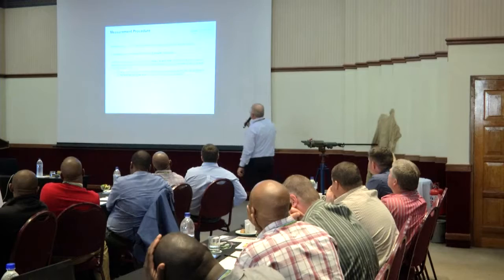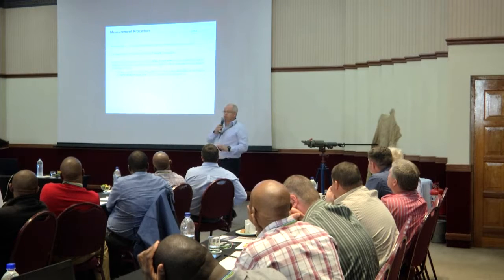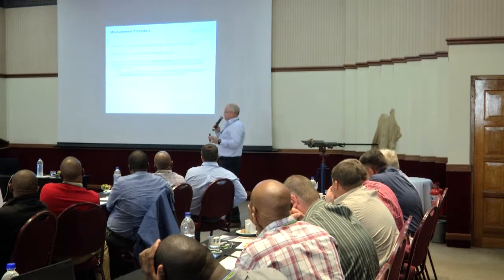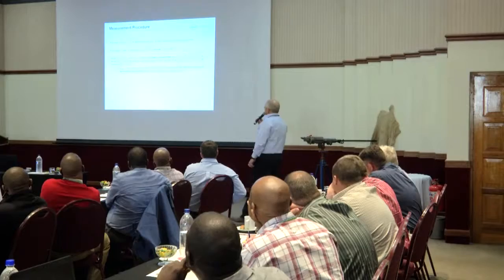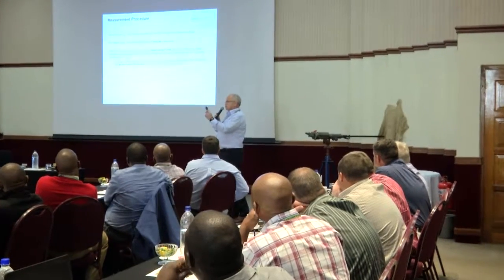The procedure: measure the LEQ for a representative time at each selected microphone position. For steady noise, when it's not something like a rock drill where there's a cycle, and I'll get to that just now, 1 minute is adequate. And the most important part, which I think one of the previous speakers also alluded to, is the cyclical equipment. Where the noise varies or is cyclical, the measurement time should be sufficient to capture variations in the noise level and include a reasonable number of work task cycles to ensure representative results. It's very, very important.